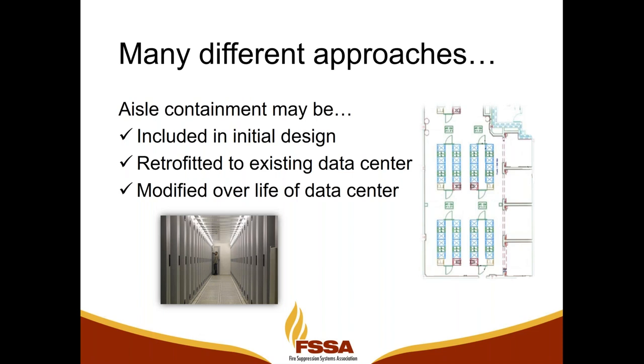And then when the containment is applied, there's a lot of variance in that. Sometimes it's included as part of the initial design of a new data center build out. A lot of times in existing data centers, as the computing load has increased, they've realized the need for aisle containment to improve their cooling efficiency. So it'll be retrofitted into the data center, and it's often modified over the life of the data center. And the key thing for fire suppression professionals is they need to realize that it's the cooling and power needs that are driving this change. And we need to be there to help remind them that the fire suppression system needs to be adjusted to accommodate their new cooling strategy. And so we've got to be creative in our ability to do that.